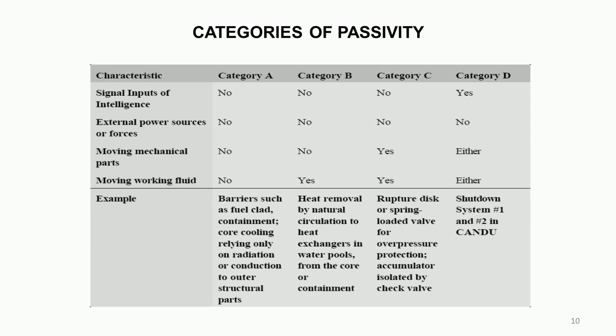Category D is differentiated by requiring an active signal input. This essentially refers to shutdown systems — any shutdown system for a reactor has to actuate on a particular signal. That signal is active; the rest of the things may be passive. This categorization helps in carrying out reliability calculations and comparing different systems for degree of passivity. Category D is the least passive and Category A is the most passive.